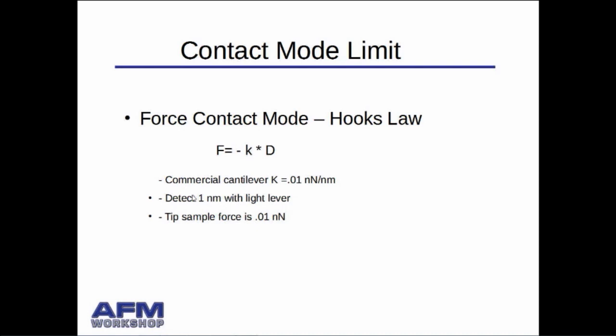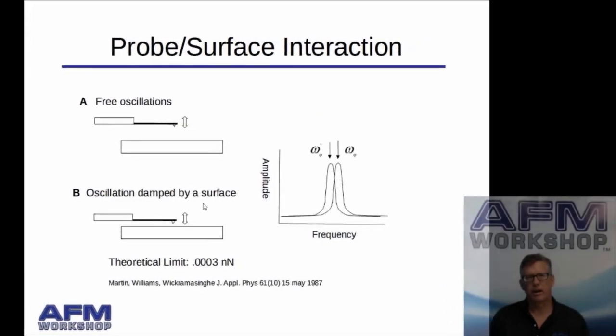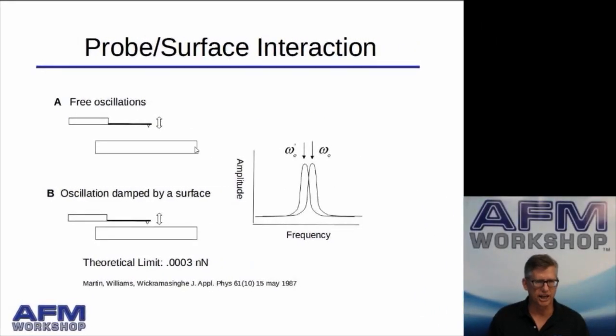But if you could detect a 1 nanometer change in the deflection of the cantilever with your light lever, then you can calculate very quickly that you can get a 0.01 nanonewton force measurement. And again, if you can detect a 0.1 nanometer motion of the cantilever, then you could get a 0.001 nanonewton. So that's kind of the limit. It's a thousandth of a nanonewton using contact mode. So vibrating mode is more sensitive.